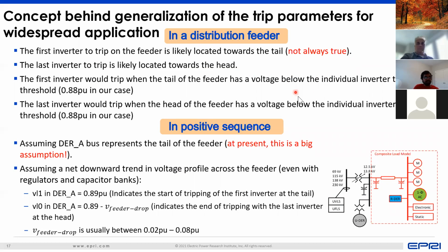And the first inverter would trip when the tail of the feeder is below 0.88 per unit, but the head of the feeder is above 0.88 per unit because there's voltage drop across the feeder. The last inverter would trip when the head of the feeder is 0.88 per unit. So it's essentially solving Kirchhoff's voltage law across the feeder for different points in time and for different voltage levels, and identifying at what are the values of voltage at which the various DER would trip.